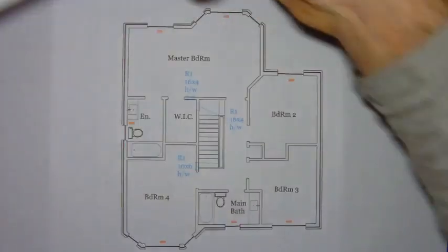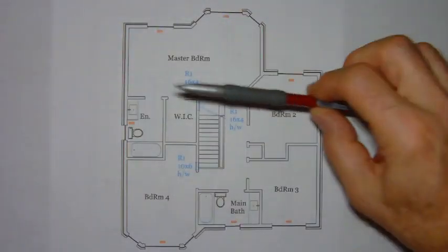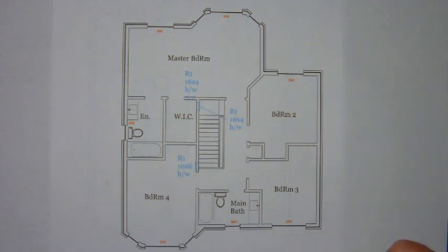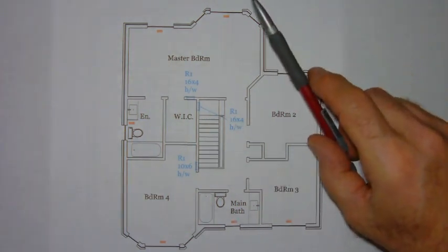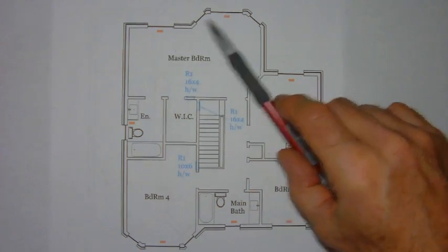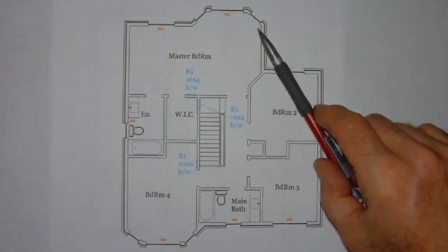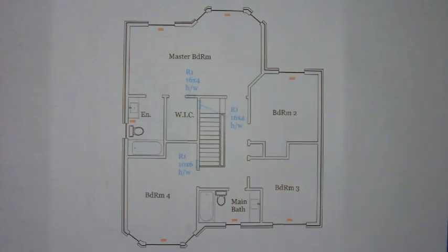However, we are at that maximum value of 80 CFM, and in looking at the master bedroom, we can see that there's a fair amount of glass. So, although our calculation may support the installation of one run, I suggest that you install 2 outlets in this room, mainly due to the amount of glass, and we want to spread out the air being supplied into this room.